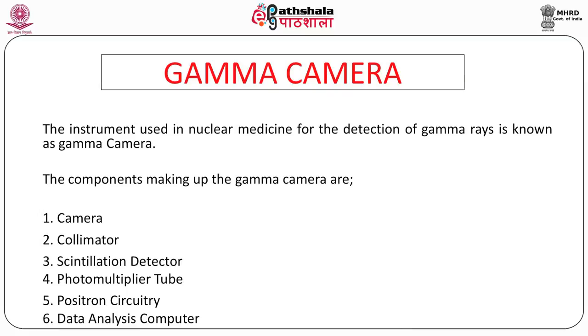A patient who has been administered a radiopharmaceutical emits radiation. It comes to the collimator, whose function is to ensure that only those radiations coming parallel — in a parallel-hole, pinhole, diverging, or converging collimator — go to the detector. The detector is a sodium iodide thallium-activated crystal. A light photon is produced, goes through the PM tube where electrons are generated, and through the positron circuitry, a computer performs the analysis and produces a quality image.